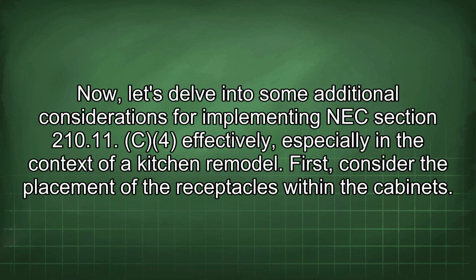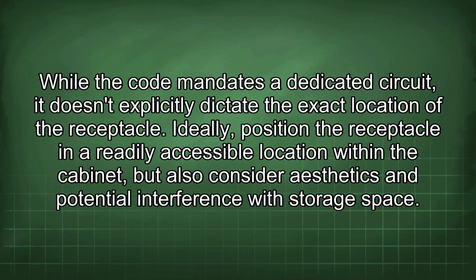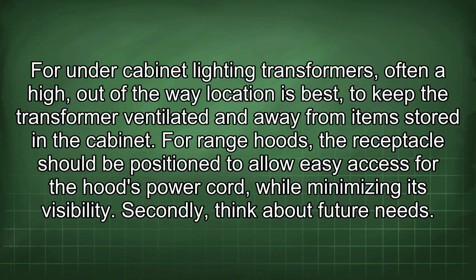Now let's delve into some additional considerations for implementing NEC section 210.11(C)(4) effectively, especially in the context of a kitchen remodel. First, consider the placement of the receptacles within the cabinets. While the code mandates a dedicated circuit, it doesn't explicitly dictate the exact location of the receptacle. Ideally, position the receptacle in a readily accessible location within the cabinet, but also consider aesthetics and potential interference with storage space. For under-cabinet lighting transformers, often a high, out-of-the-way location is best, to keep the transformer ventilated and away from items stored in the cabinet. For range hoods, the receptacle should be positioned to allow easy access for the hood's power cord, while minimizing its visibility.